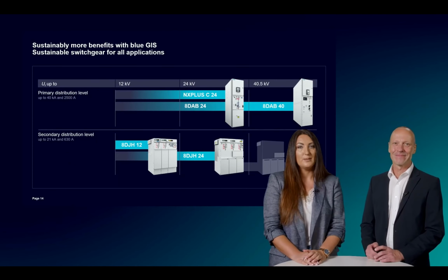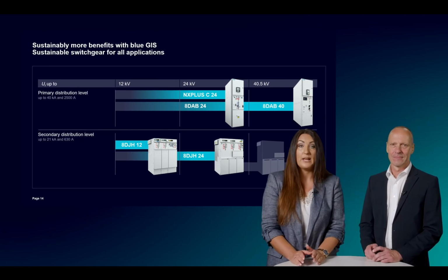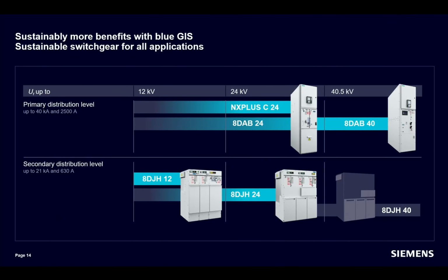I will do. So the good news is that on the primary distribution level, up to 40 kA and busbar and feeder current up to 2,500 amps, we already have a portfolio available up to 24 kV as an SF6-free switchgear. We have available two types of switchgears, so-called NX plus C24 for the busbar current up to 2,500 amps, feeder current up to 2,000 amps, and short circuit current up to 25 kiloamps. This switchgear is available for single busbar system at the moment and is also available at the exact same footprint as NX plus C product, which is our well-known SF6 product.